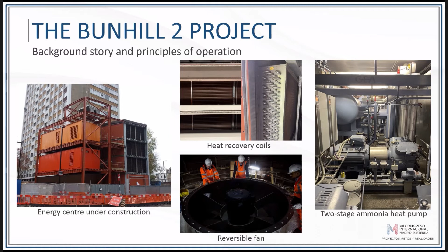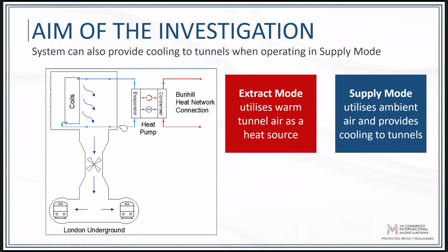And just to talk a little bit more about our role in the project and our investigation, as I've said, the system can operate in 2 different ways: extract mode and supply mode. Extract mode works by removing hot air from the underground tunnels and using that air as your heat source. And the system can also operate in supply. So you change the direction of the fan, and in that way, you can actually recover heat from ambient air. And after that air is cooled down, it can be supplied to the tunnels, therefore providing some cooling to nearby stations as well. So it's a bivalent system.